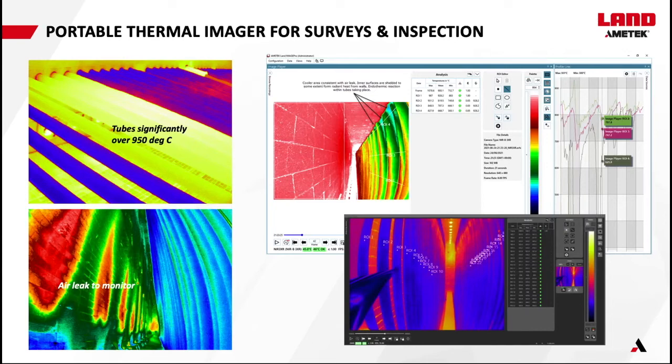And actually what we saw on the top right-hand side is the same furnace where we saw an issue with tube leaks, and that was producing a huge amount of air ingress and really having an effect on those tube temperatures. That actually may not have shown, again, from the Cyclops. Customer may have been able to see that visibly with the lower tube temperatures towards the top of the furnace. But we were able to identify just how low those temperatures were, in some cases lower than 650 degrees C. So really concerning. But by fixing that issue, by addressing those tube seals, the customer spotted a real reduction in their fuel consumption. So they're really able to improve the efficiency of that process, which again is a key priority at the moment.